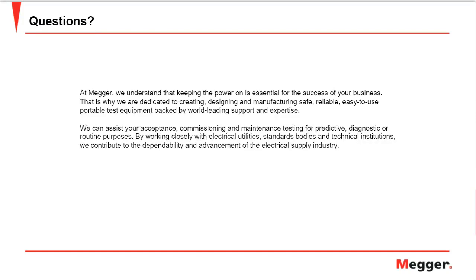Thank you for that. So for predictive maintenance and for typical motor repair, probably well over 99.9% of the tests, as far as between the AC or DC high pot, it's the DC high pot. AC high pot is used almost exclusively in motor manufacturing, not totally exclusively, but mostly in motor manufacturing. It's an Underwriters Laboratories recognized test. It's usually a requirement for production line OEM motors. And so they will do the test there.